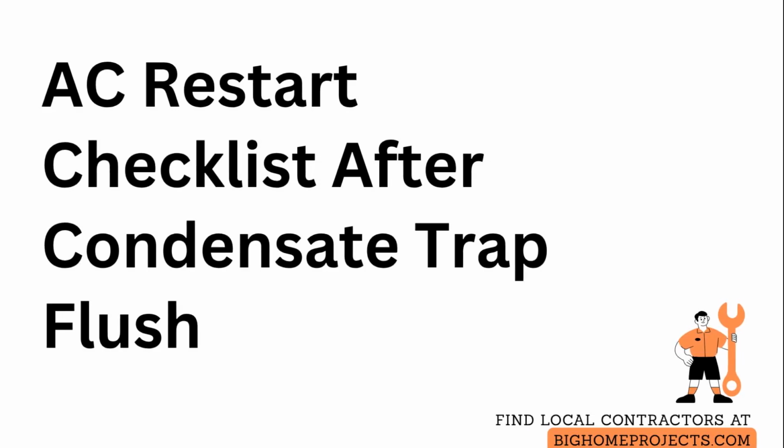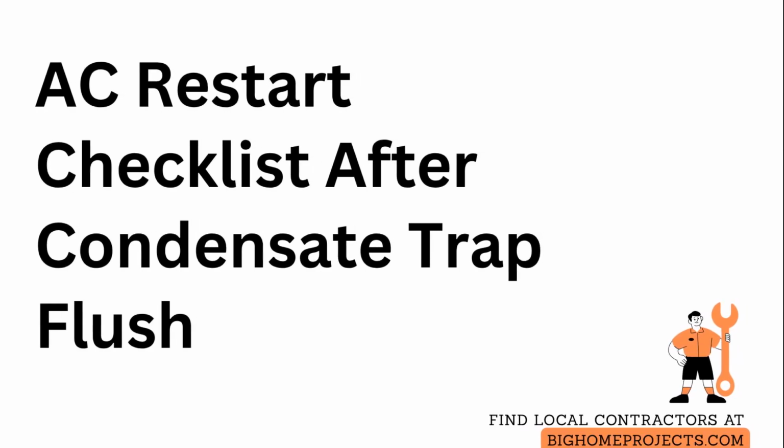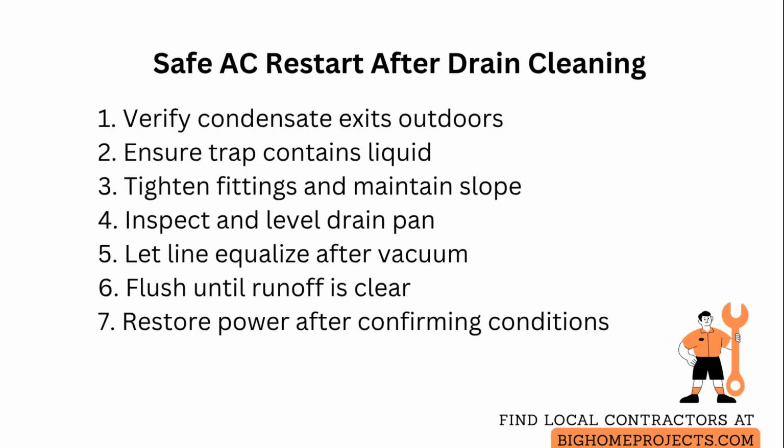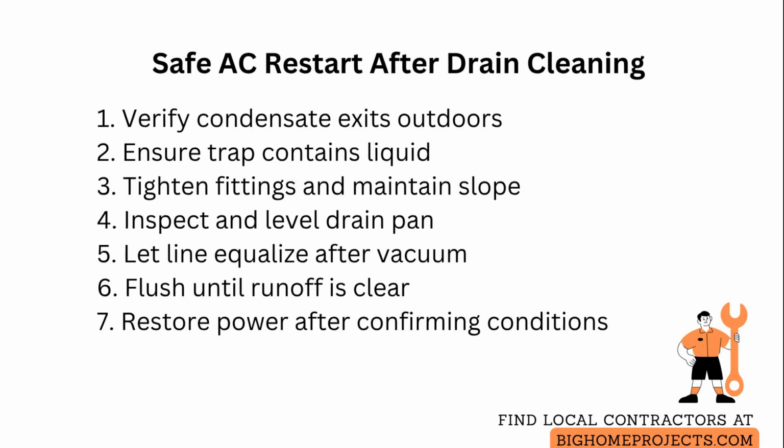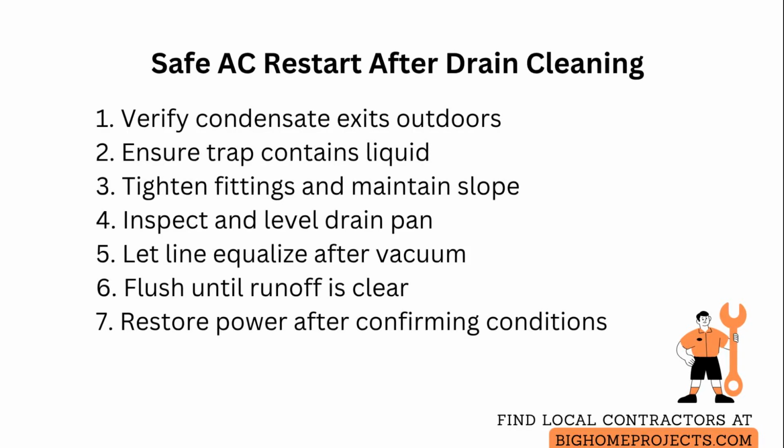Can we run the air conditioning system immediately after cleaning the condensate drain line? After cleaning the drain line, verify the condensate actually exits to the outdoors and that the trap shows liquid inside, so air cannot siphon through and allow water to leak into the system.